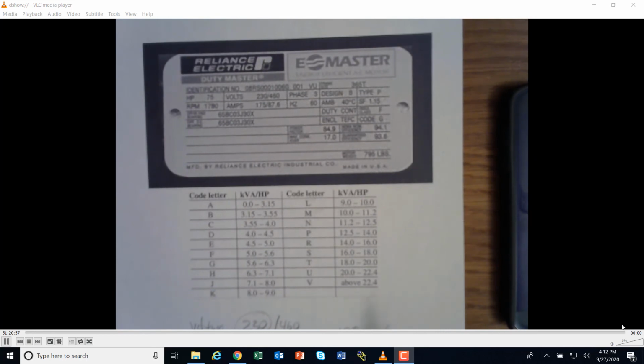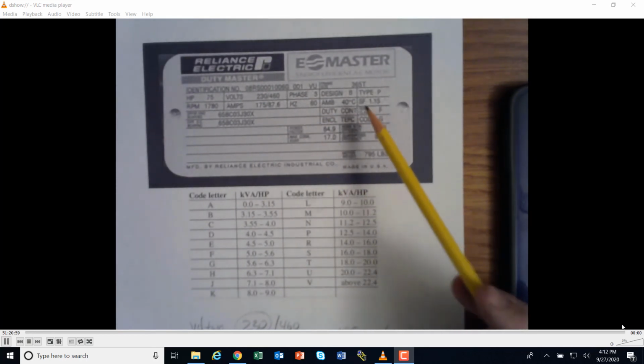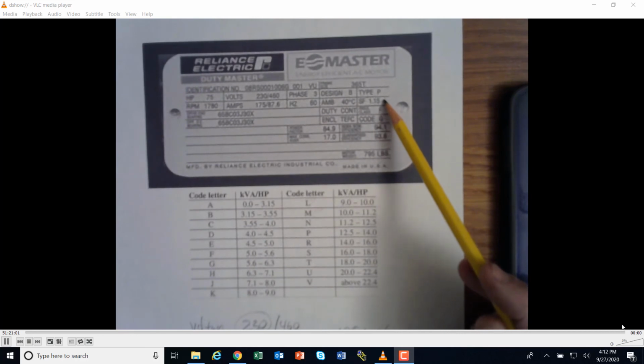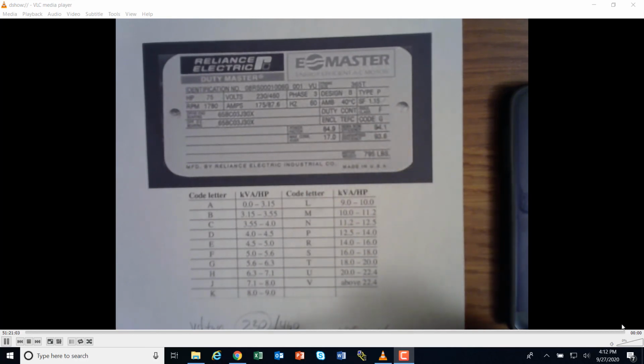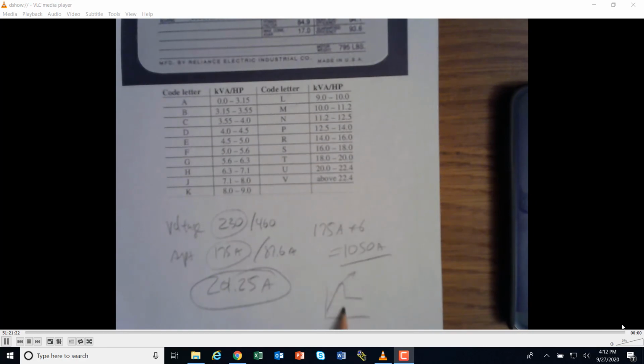Okay, so that's kind of how you read some of the things off of this nameplate, specifically the service factor amps. You multiply by 1.15, and you want to keep that in mind when you're sizing the continuous or steady state circuit breaker and circuit protection, and also the locked rotor amps is what you'd want to keep in mind when you're doing your time delay here as well.